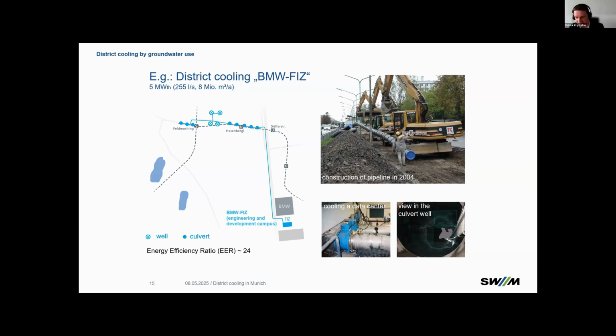On the lower right side, you can see the culvert. There's the water, the collected water that goes underneath the subway. And here we place our pump in it and connect it to the pipes, as you can see on the upper right. For groundwater, we use plastic pipes, uninsulated, because the groundwater has the same temperature as the soil around, so we don't need to insulate the pipes.